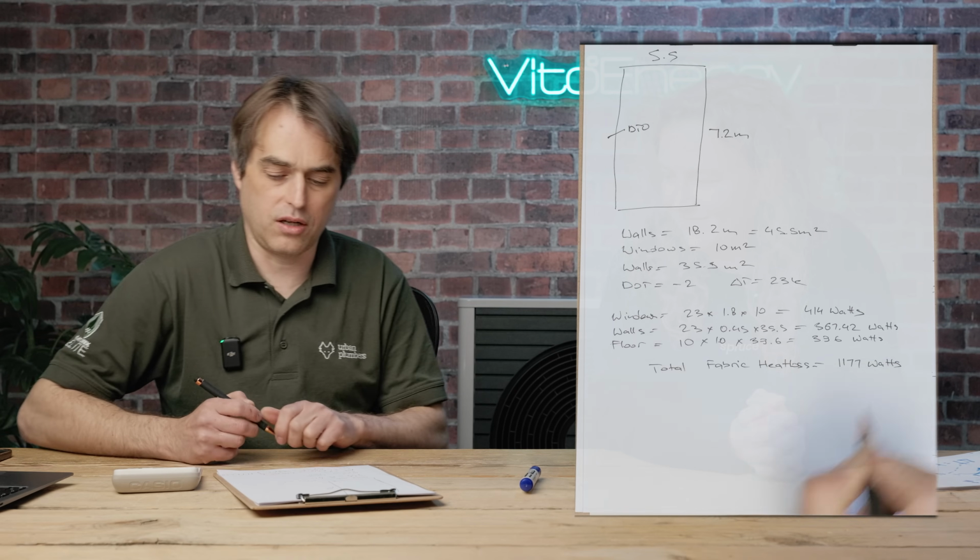It's 1177.42, so 1.2 kilowatts. You've missed the ventilation heat loss, which yes, in loads of cases can be 50%, even more of the heat loss. So super important factor. How do we calculate those?